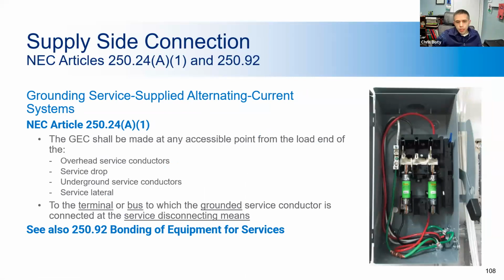So here we see a supply side disconnecting means that has proper neutral and ground bond in accordance with the code. This was actually done correctly. You can see here the white neutral conductor entering from the top on the left side, and the green bonding screw effectively bonding the neutral to the enclosure and to the ground. So that was done correctly.